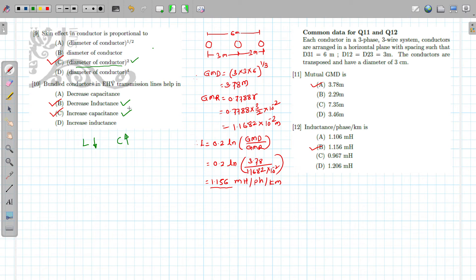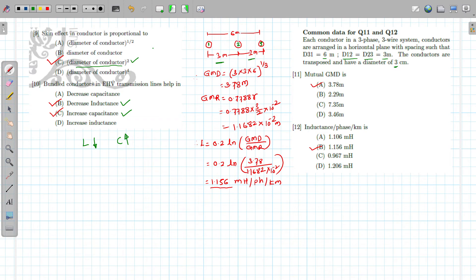Common data for Questions 11 and 12: In a three-phase three-wire system, conductors are arranged in a horizontal plane. Spacing: d12 = 3 m, d23 = 3 m, d31 = 6 m. Conductors are transposed and have a diameter of 3 cm. First, we determine the mutual GMD: GMD = (3 × 3 × 6)^(1/3) = 3.78 m. So the first option is correct.